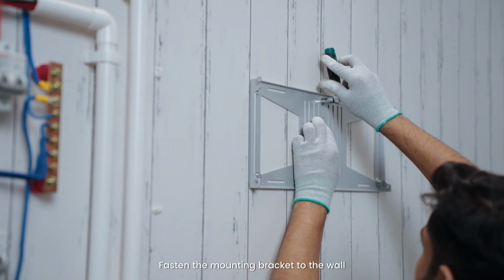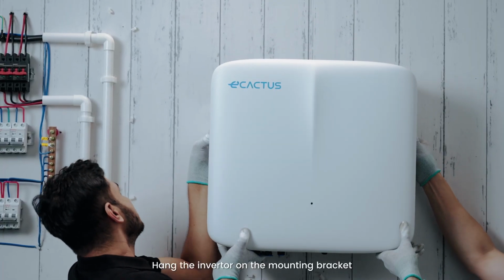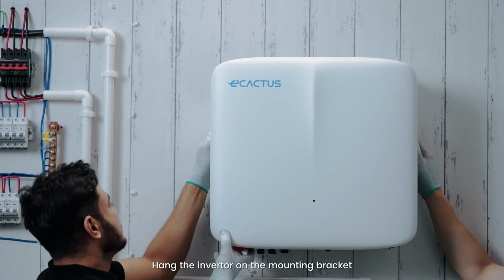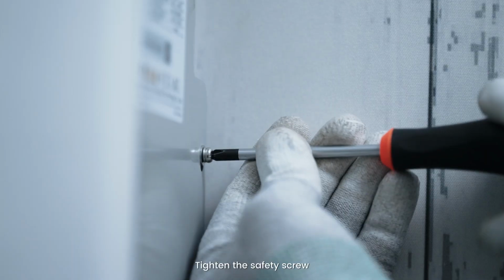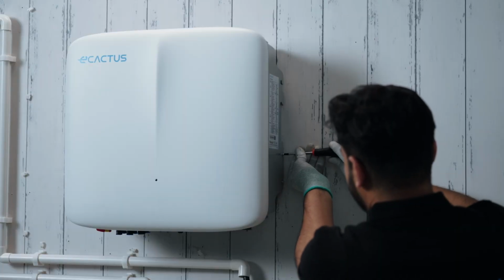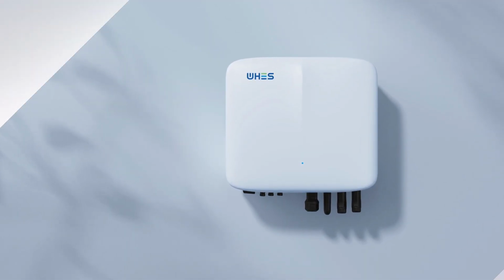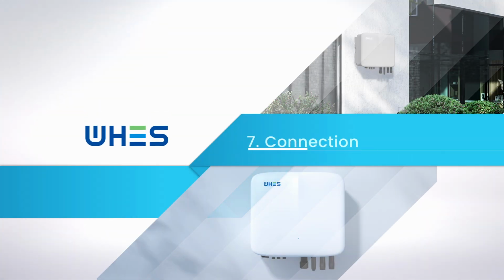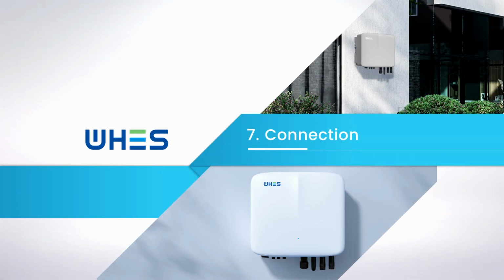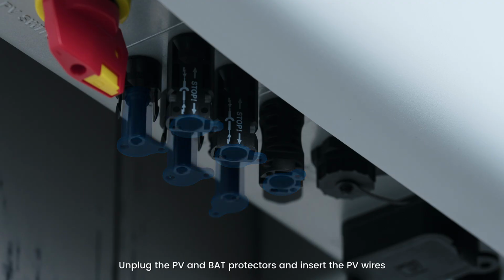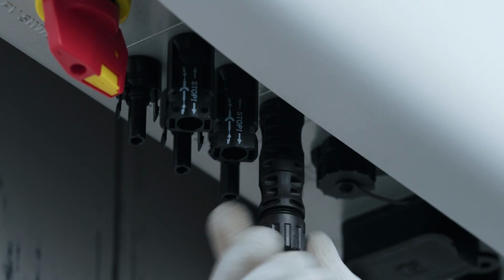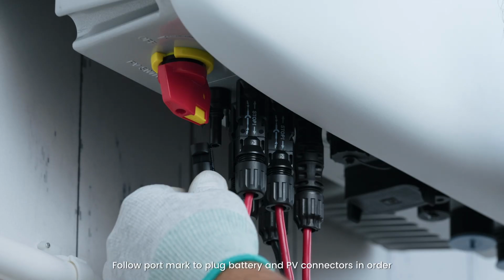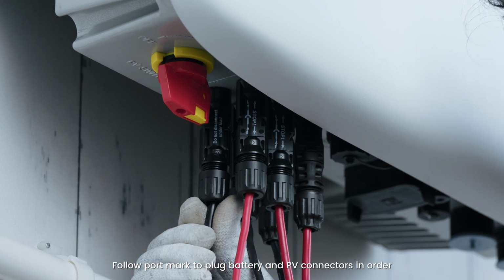Fasten the mounting bracket to the wall. Hang the inverter on the mounting bracket. Tighten the safety screw. Unplug the PV and the bat protectors and insert the PV wires. Follow the port mark to plug battery and PV connectors in order.